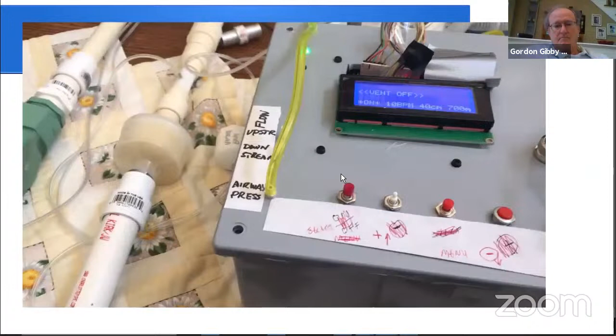There's an expiratory valve here, but instead of being electrically controlled, that one's air pressure controlled, and we control it electrically through this solenoid valve using some of the driving pressure to control whether or not that valve's open or not. To save space, we had to go around a U, and then we use this filter to smooth out the flow again. And then this part right here is fascinating.